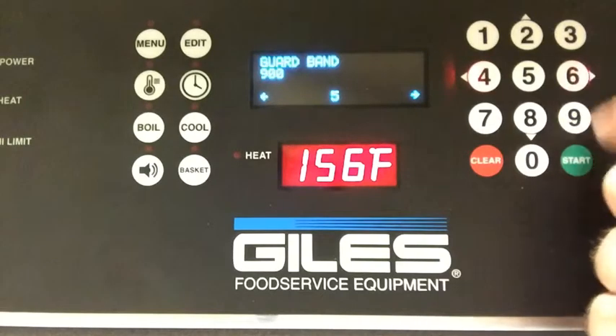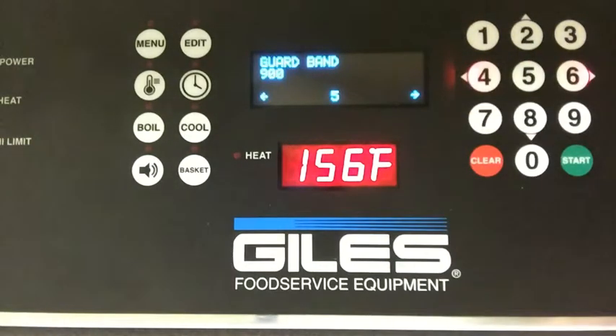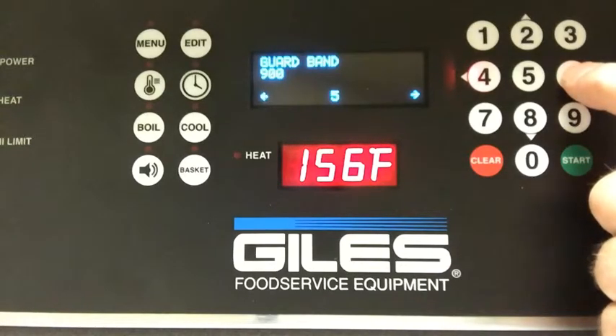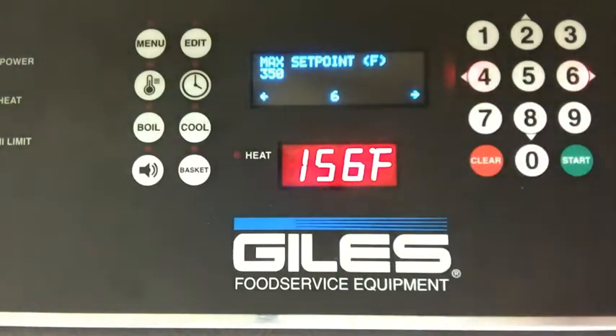It wouldn't even matter. The guard band is always going to be set to 900. No need to change that. That's a factory default setting. The maximum set point, saw that earlier, 350 degrees. When I tried to bump up to 355, it would not let me do it. It'll go down, but it will not go over 350 degrees.